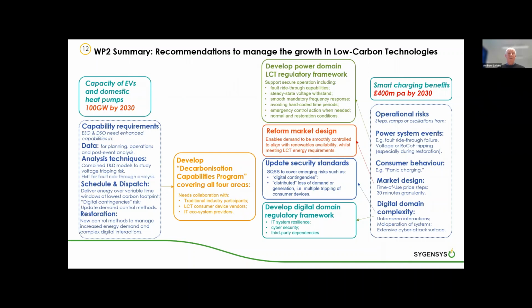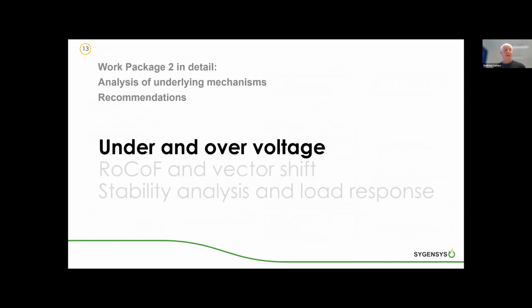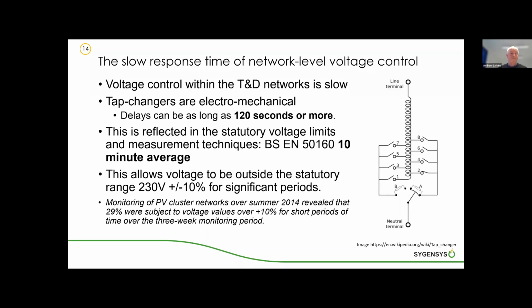So moving on from those top level recommendations, we're going to go through and talk about Work Package 2 in a little more detail. We have selected just a few topics from this, going through under and over voltage, RoCoF and vector shift, and stability analysis and load response. And I'll start by talking more about under and over voltage. So in electricity grids, voltage control response times at network level typically tend to be fairly slow. Voltage control is undertaken through mechanisms such as tap changers, which are electromechanical.